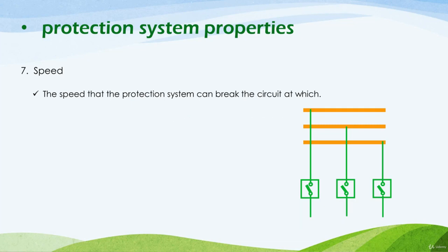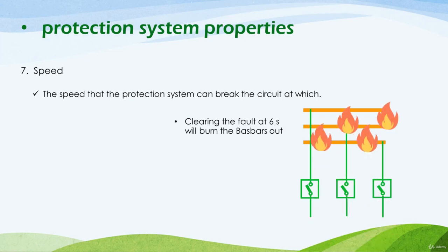But suppose now the protection system takes a longer time to break the fault, about 6 seconds. This means the protection system is very slow to take action, or it's not fast anyway. In that case the bus bars cannot withstand the full current passing through them for 6 seconds, and they will be burned out, or may fail, due to the long time that the protection system takes to break the circuit.